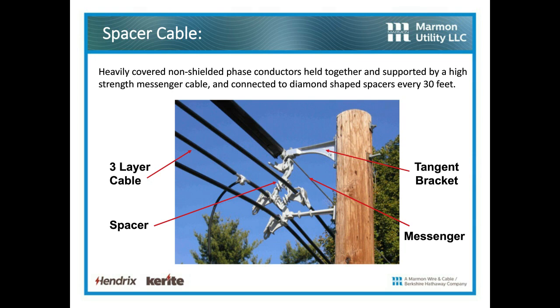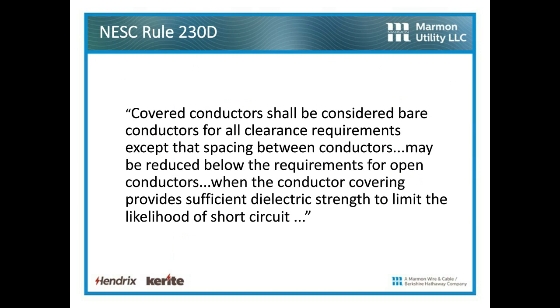And lastly, we have a couple of brackets: tangent bracket, dead-end bracket, angle bracket, and that's it. It's a very simple system. We're covered by the National Electric Safety Code that says essentially if you have good insulation on that conductor, you can move those phase conductors closer together. It doesn't say how close we can move those phase conductors together.